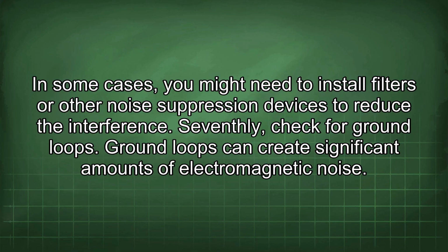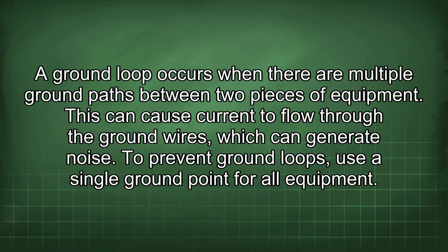Seventhly, check for ground loops. Ground loops can create significant amounts of electromagnetic noise. A ground loop occurs when there are multiple ground paths between two pieces of equipment. This can cause current to flow through the ground wires, which can generate noise. To prevent ground loops, use a single ground point for all equipment.